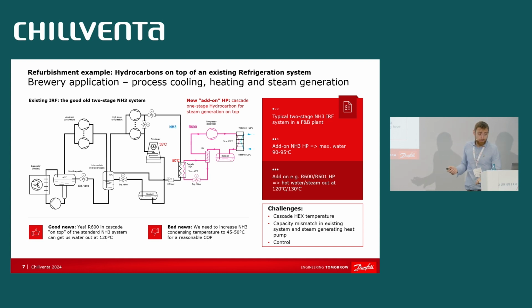I'll wrap it up. Hydrocarbons are good for new projects, can be also good for existing refrigeration systems. However, it's a bit more challenging to integrate. And we talk a lot about hydrocarbons. They are fantastic refrigerants, but people are getting nervous from them. Why? Because they are classified as explosive. Now, yes, they are classified as explosive. However, we need to treat every refrigerant with respect. And this applies the same for the hydrocarbons.